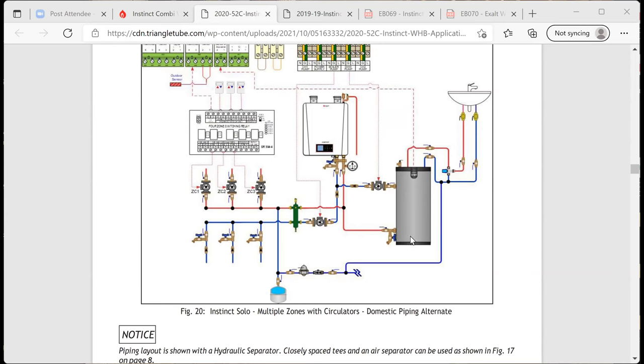Do it this way, we've had no issues. I've seen guys do the boiler pump on the return and they'll do the supply pump on the other side. And then with closely spaced T's, I've seen delta T issues with this, with delta T lockout. So if you're doing your indirect on the primary side, just put both pumps on the return with check valves installed, pumping into the boiler, and your supply line's just going out to the indirect and your header or closely spaced T's, and you'll have no issues with that.